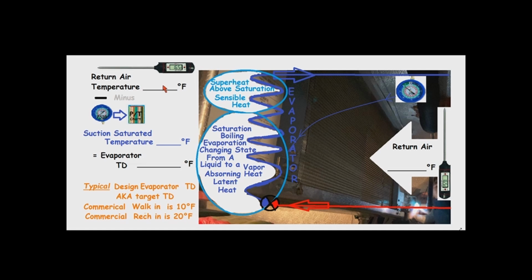We'll do some other paperwork, listen to a podcast, do some studying, but I want to make sure that temperature actually gets there. Now, when that temperature is about to cycle off, then my suction saturated should be right on the money. Let's say I'm at 35 degrees, 35 minus 10, I should be right at 25 degrees suction saturated. And whatever you convert that to in pressure will be your quote unquote correct pressure. But that TD gives us a lot better, a lot more precise thing to work with.